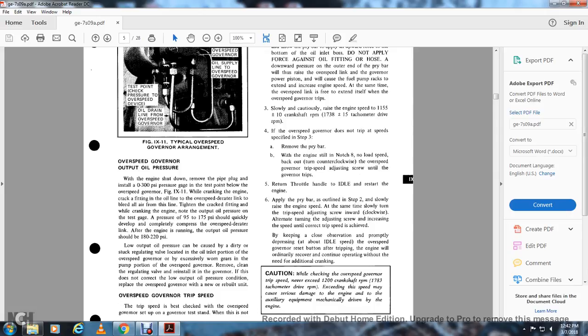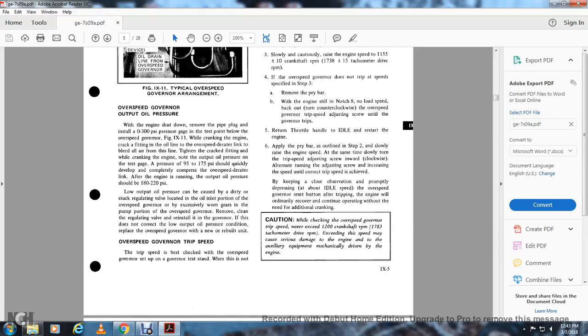Slowly raise the engine speed while simultaneously slowly turning the trip speed adjusting screw inward (clockwise), alternating turning of the adjusting screw and increasing speed until the correct trip speed is achieved. Keep a close watch and promptly depress the idle speed button after tripping. The engine will ordinarily recover for continued operation without additional cranking. Caution: while checking the overspeed governor, never exceed 1200 crankshaft RPMs or 1783 tachometer drive RPMs, as exceeding this speed can cause serious damage to the engine and auxiliary equipment driven by the engine.